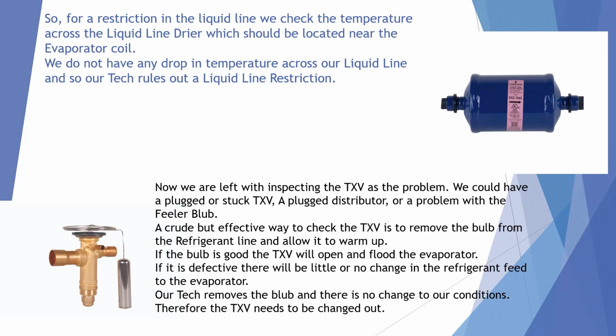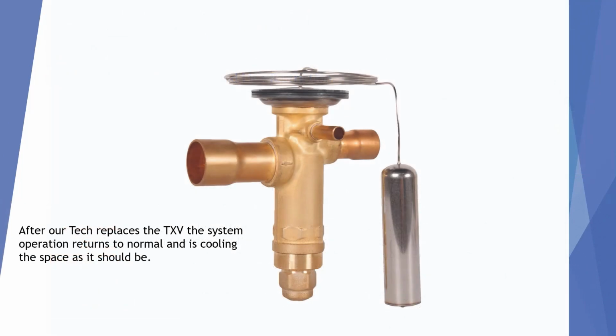Our tech removes the bulb and there is no change to our conditions. Therefore, the TXV needs to be changed out. After our tech replaces the TXV, the system operation returns to normal and is cooling the space as it should be.